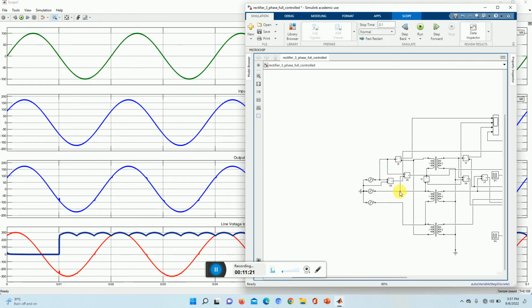Then we are measuring between R and Y, which is the line voltage, and this leads the phase voltage by 30 degrees. That's why the blue line is a little higher. We know the line voltage is root 3 times the phase voltage, so since the phase voltage peak is 100, this becomes 100 root 3, about 173, which we can see around there. So this is the line voltage.